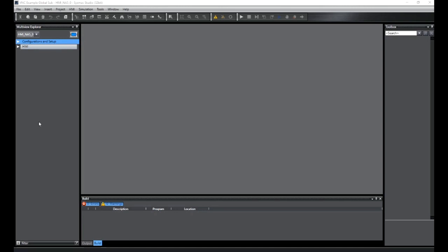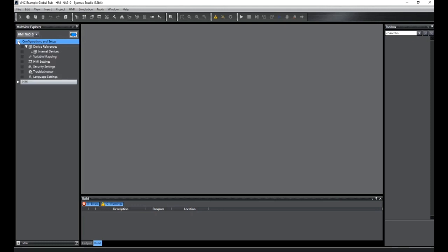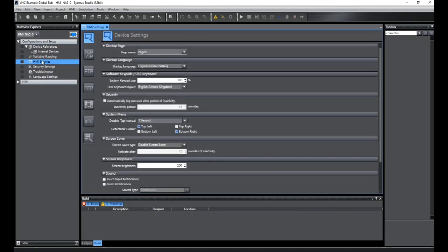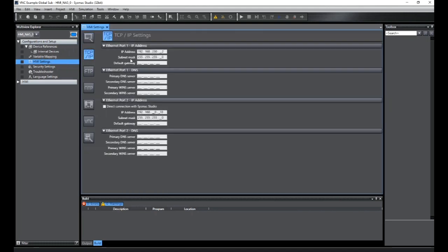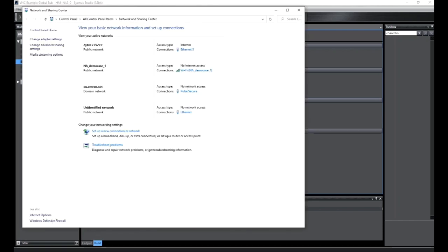In order to configure the HMI, we bring up the SysMac Studio tools. This is one I prepared earlier. Here we can see we've got an NA5 version 1.2 device ready to go. Look at the configuration and settings. In here, I'm going to look at the HMI settings, and underneath here, the TCP IP, I can see my IP address for port 1 and my IP address for port 2. This is going to correlate to the network settings I have on my computer.